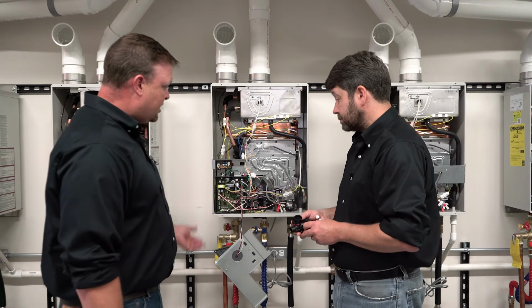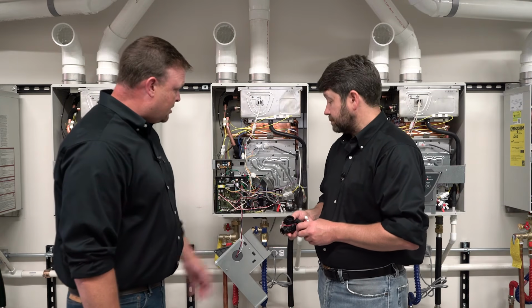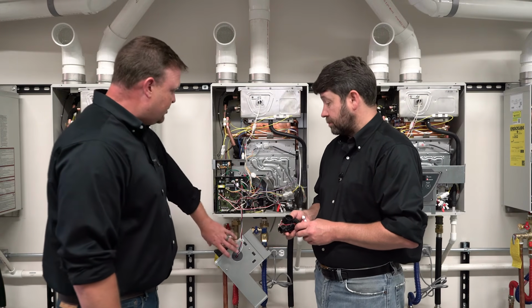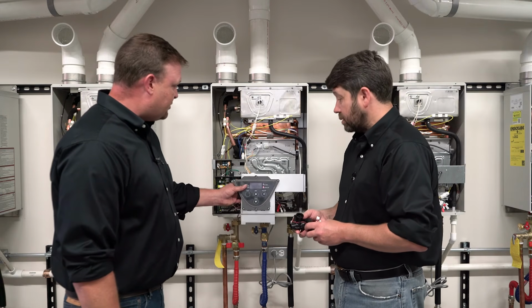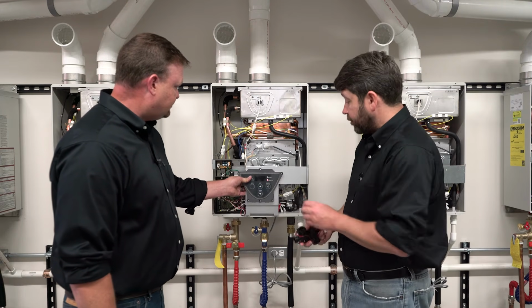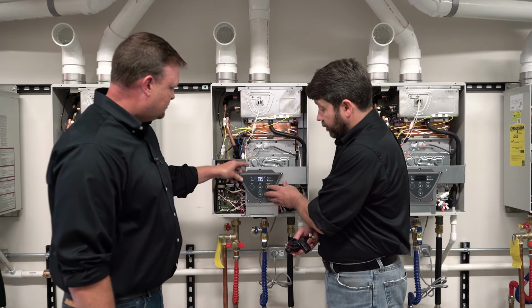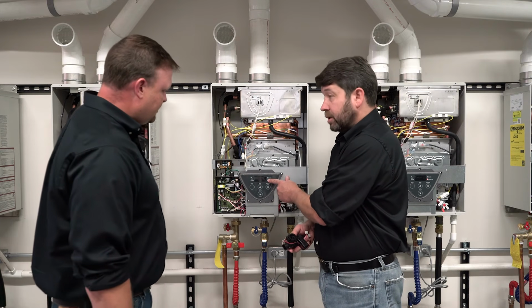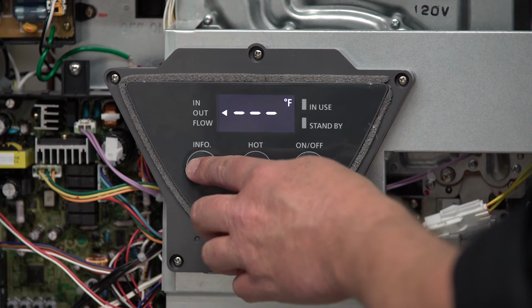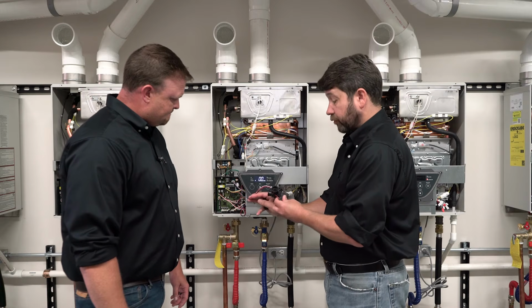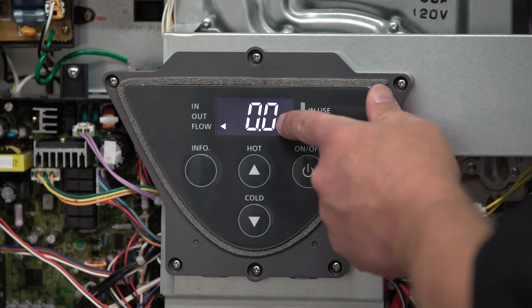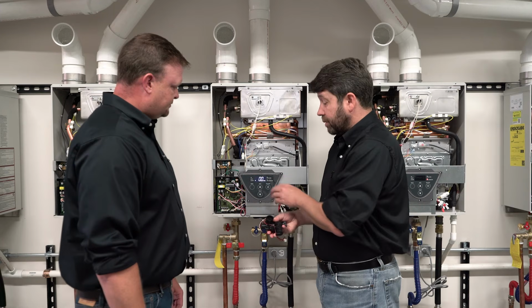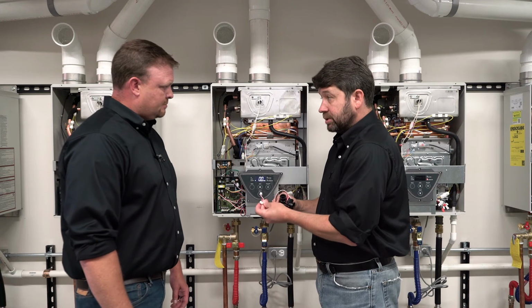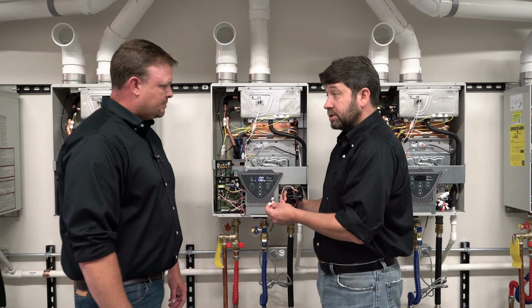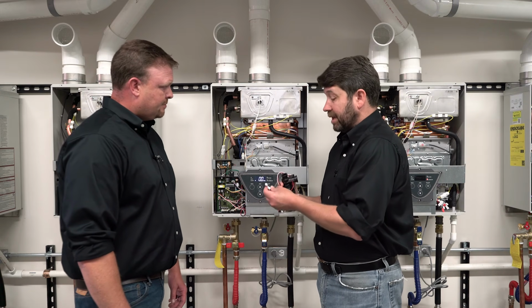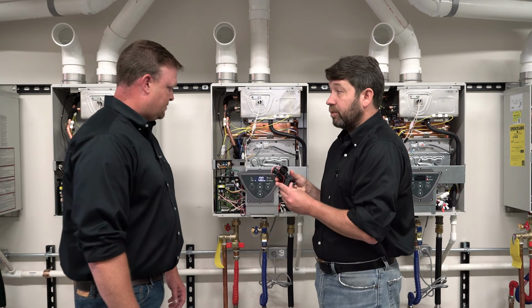So that's an easy way to check, just to make sure that we're getting water flowing through there and it's actually detecting it. Can we use the control and see if our gallons per minute is actually working while you do that? Yeah, absolutely. One thing we want to do though is push the on-off button here on the control so that the orange light goes into standby mode. What that will do is let us still look at our diagnostic information, and with the flow sensor removed but still connected to the control board, when we blow through it and it spins the impeller, we should see some flow registered here. If the impeller spins but we don't see any flow registered, we can unplug these connections and plug them back in, and that will clean the electrical connections. That will take care of the problem most of the time. And if we still don't see flow after doing that, we're going to replace the flow sensor.